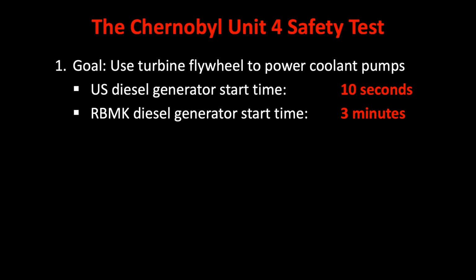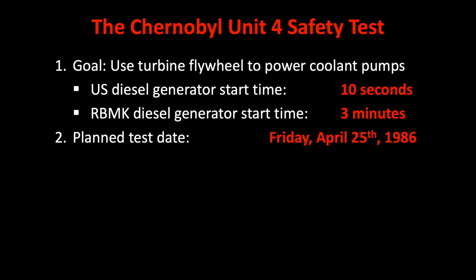Engineers at Chernobyl postulated that they could use inertia from turbine flywheels to power the coolant pumps for about 40 to 50 seconds after losing off-site power, and they sought to confirm this theory during the ill-fated safety test at Chernobyl Unit 4. Now, the original plan was to perform the safety test on Friday, April 25th.